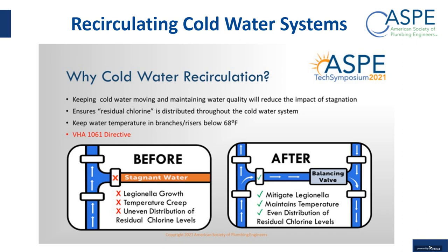Basically, the VA feels it's really good, and I think a lot of scientists feel it's really good to keep that water moving. When you have a stagnant line, it's an opportunity for not only Legionella, but other waterborne pathogens to grow in that stagnant line. By having that water constantly moving, it basically ensures that the residual or free chlorine in the system is distributed evenly throughout the cold water system and not just be in certain locations. And it keeps the water temperature even throughout the system. You may have hot spots and things like that. By recirculating the cold water, you're going to keep the temperature even throughout the system. And then there's the VHA 1061 directive.